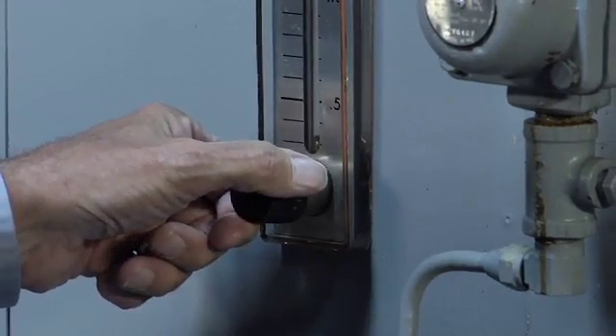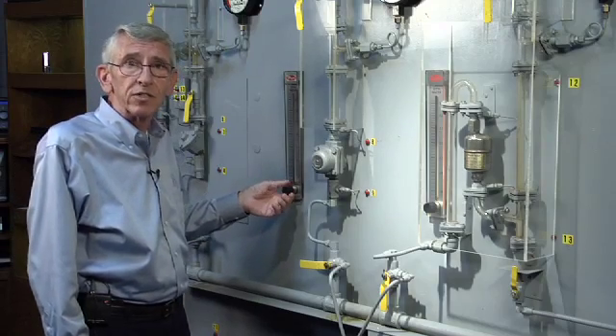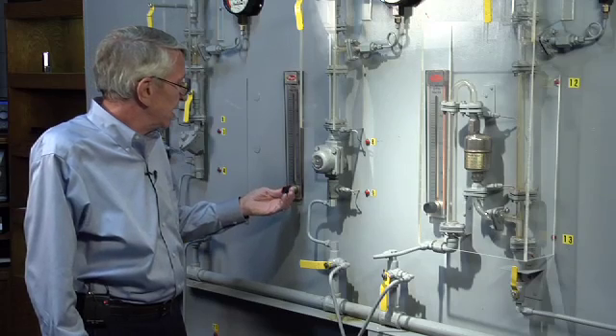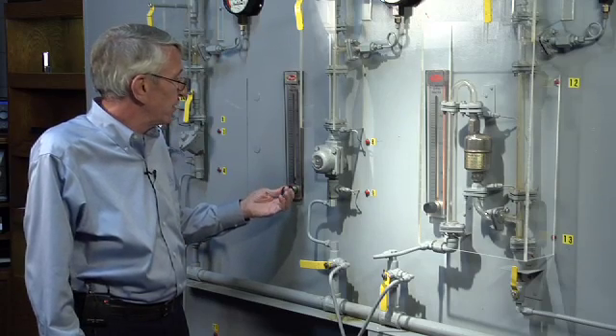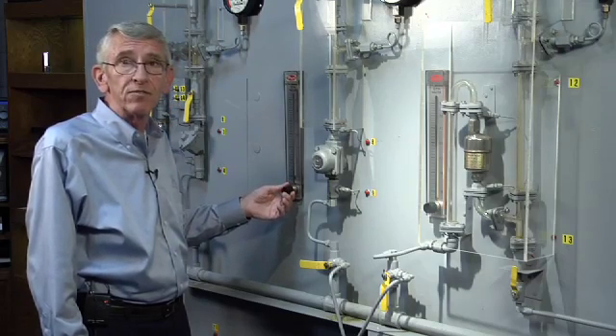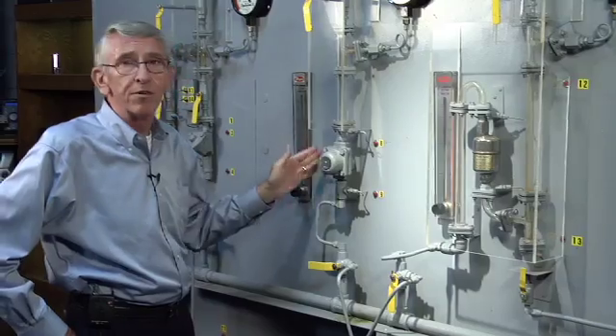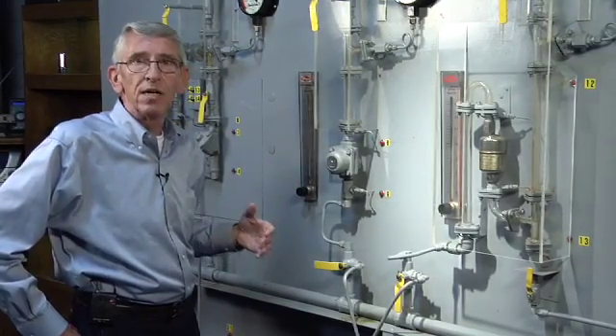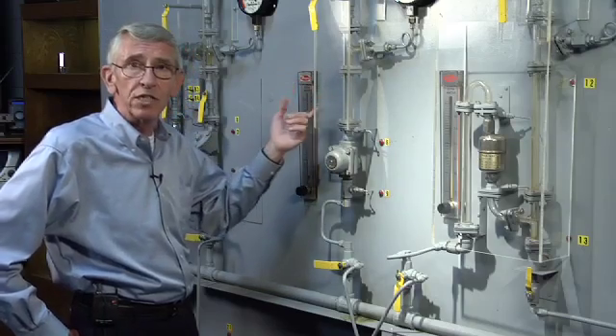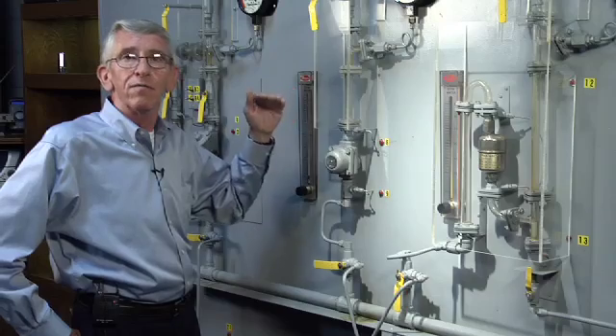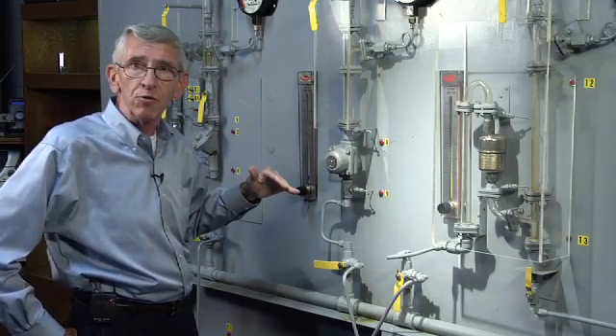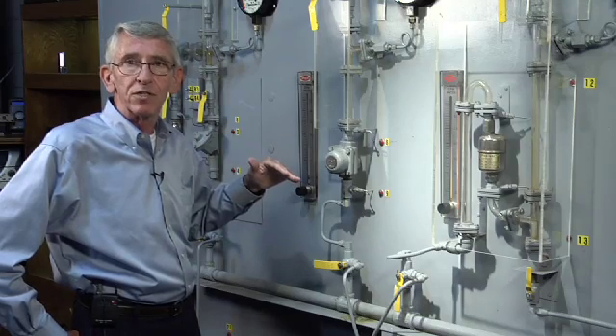If I provide a water flow of 0.5 GPM to the shell and tube heat exchanger with 15 psi steam feeding it, I should be providing a load of only about 60 pounds per hour of condensate to the trap. If you'll note, I'm already backing up the condensate, even at only a 60 pound an hour load. I'm backing up condensate ahead of this bimetal thermostatic trap, because that is the nature of any thermostatic trap. I have to lose heat energy from the condensate in this line for the temperature to go down far enough for the trap to open and drain. While I'm waiting for that temperature decrease to occur, I'm backing up condensate into the equipment.